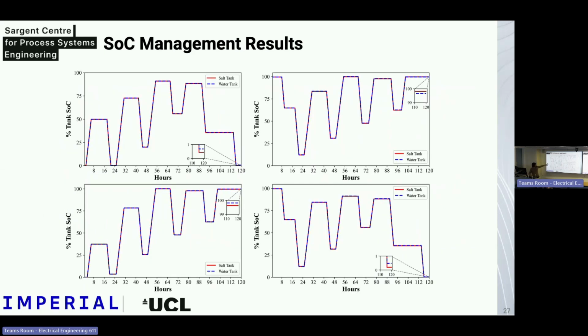We can look at the state of charge of the system over this 5-day time horizon. The red shows the salt tank and the blue shows the water tank, and we see they overlap almost perfectly. This shows the power and feasibility of the state of charge management algorithm, both in-cycle, where it only deviates around 0.3% at the end between them, and over the whole simulation horizon, where it doesn't go over or below the limits. Both state of charge management algorithms work quite well.